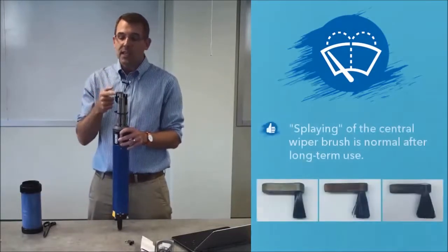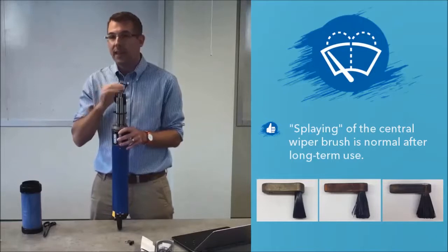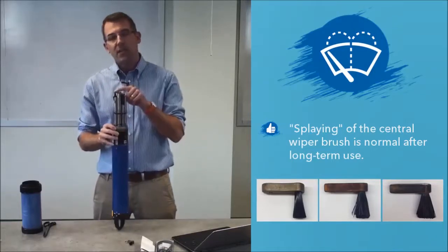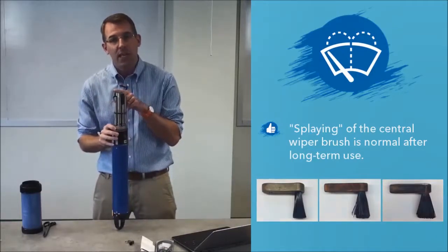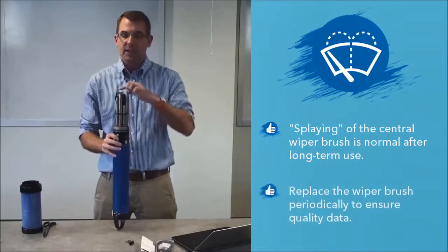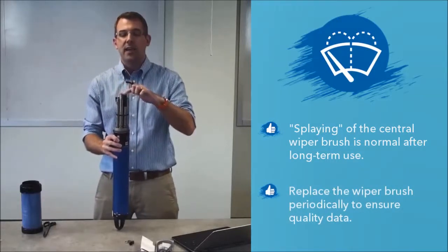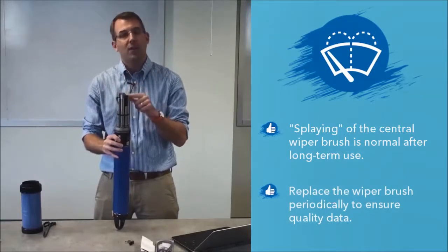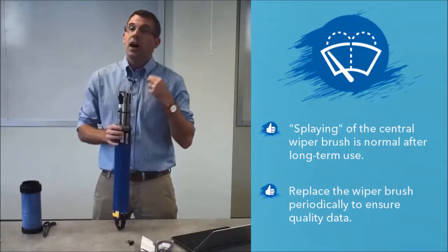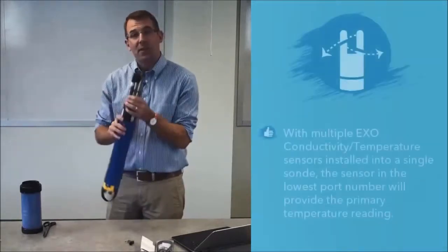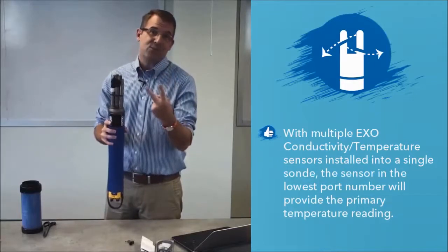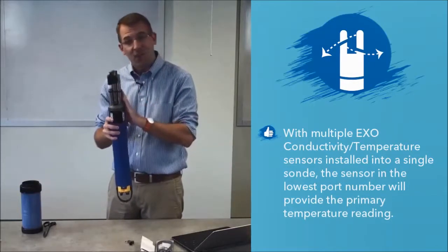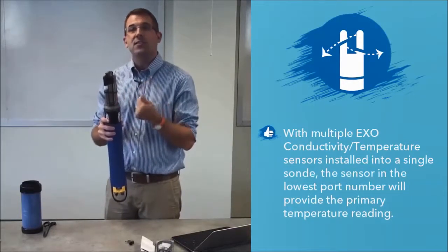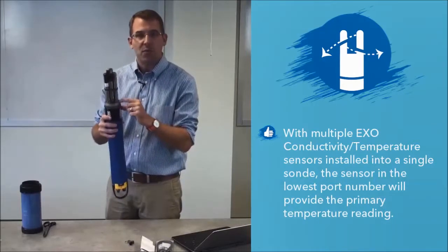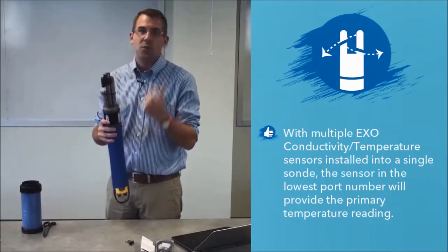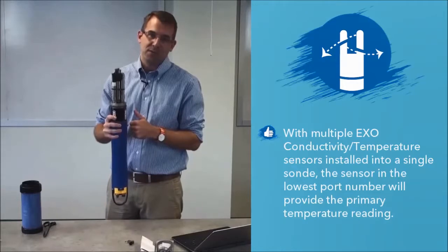With Wipe CT, you will notice brush splay, and that's normal. So pay attention and keep the wiper brush clean and replace it periodically to make sure that you're getting optimal contact with the wiper brush and your conductivity cell. Another neat feature, because of the plug-and-play sensors, is you can have 2 conductivity temperature probes installed in the same sonde. Just note, whatever temperature probe is installed in the lowest port will be used as your primary temperature reading.